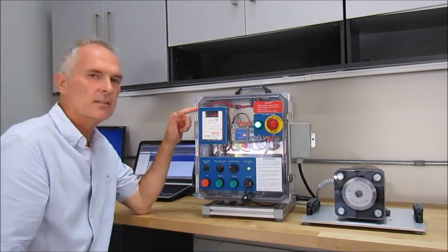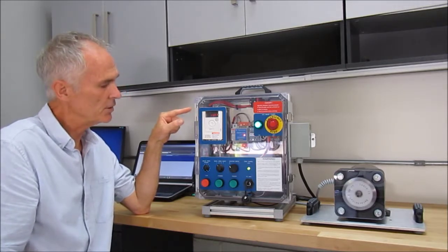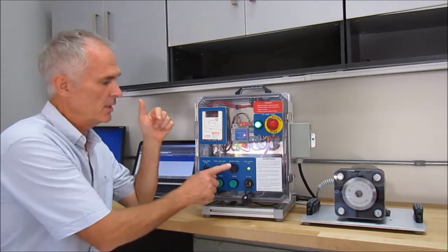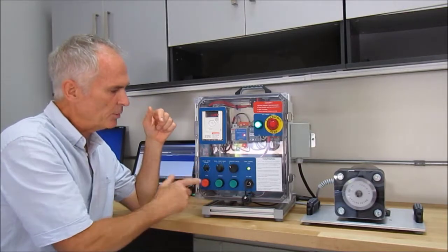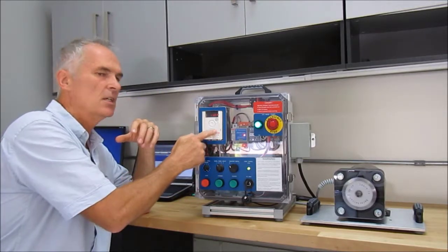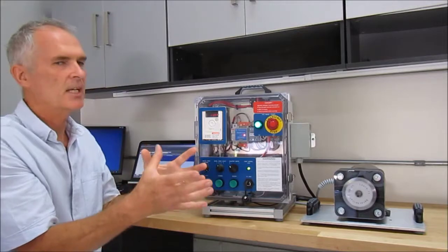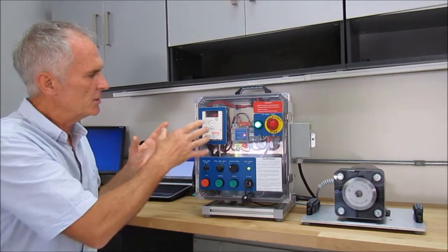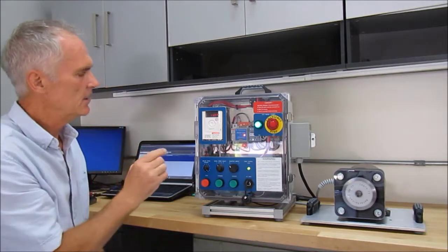One of the other things that I want to talk about is running the drive in local mode. There's two ways that we can control the drive. We can control it using remote devices like a temperature actuated switch, a pressure switch, or a float switch, or it could be an HMI device like a selector switch or a push button, or any device to control it remotely. So in some cases you may want to just control it locally, okay, for troubleshooting reasons, or you may have an application like a mixer or a food processor, a little conveyor, or even a little drill press where you want to just operate it from the drive keypad and you don't need any remote devices. Okay, so I'm going to show you how to do that.